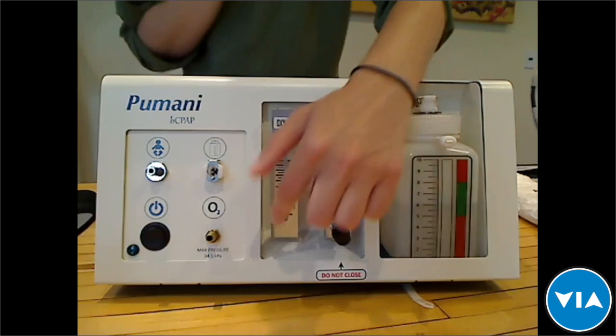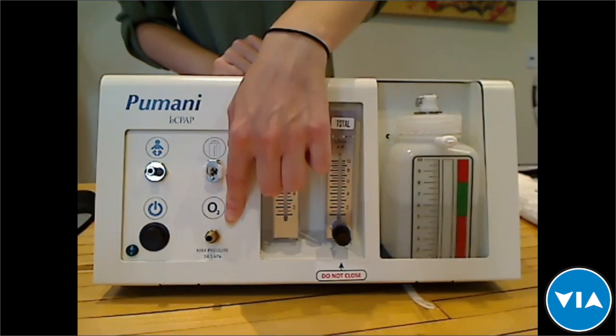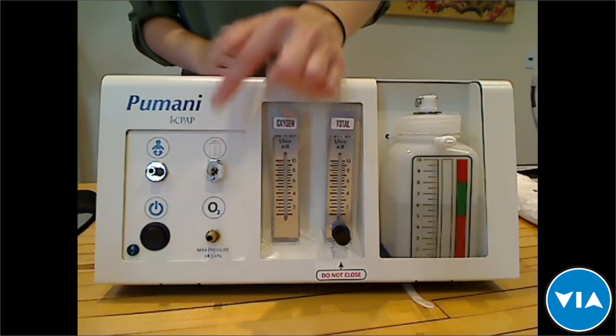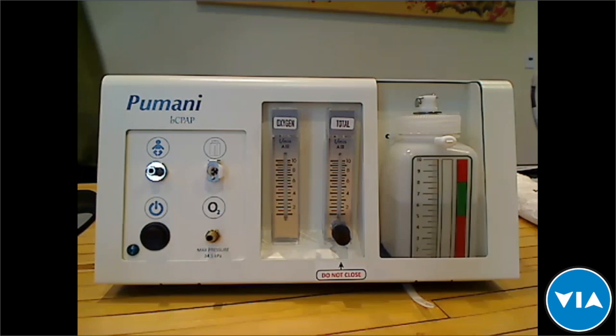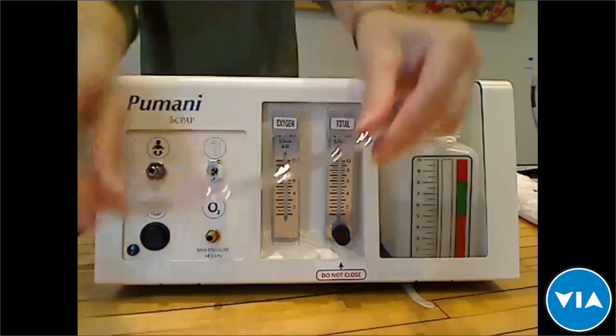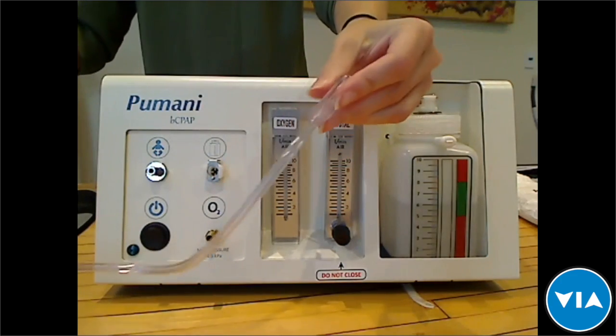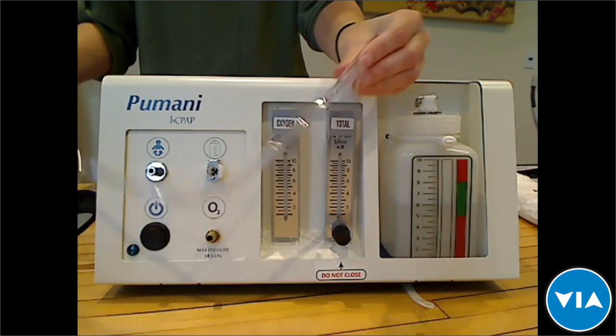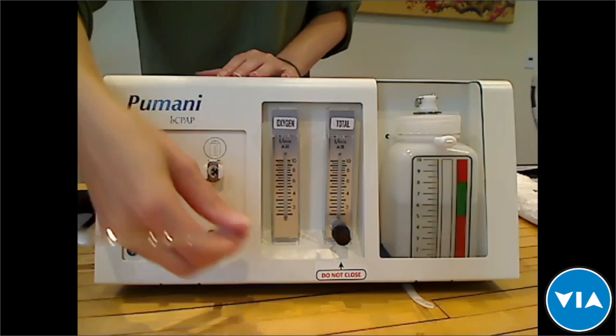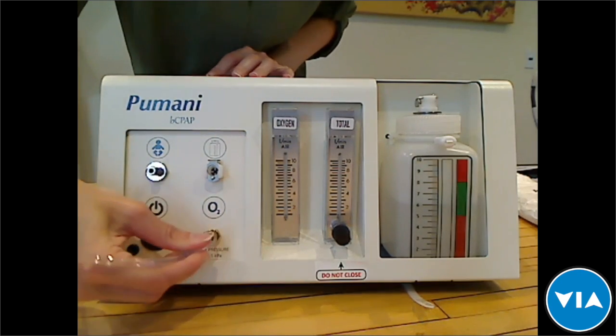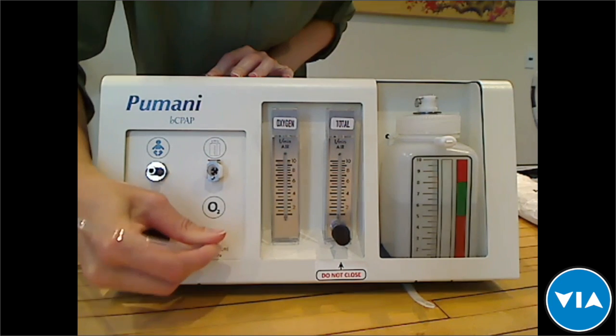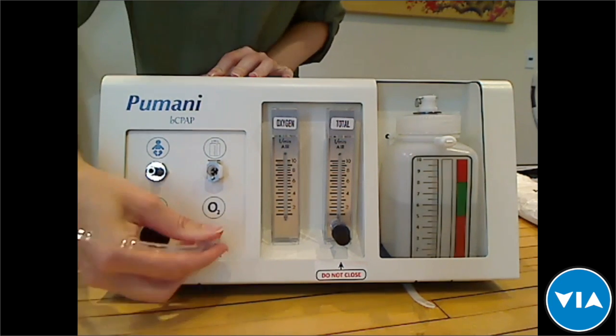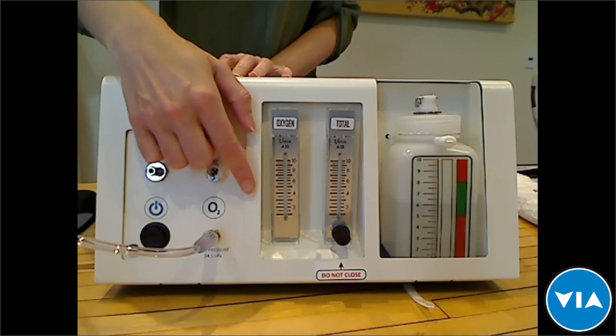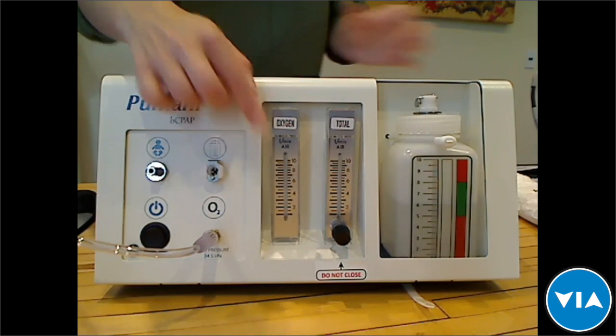So there is the oxygen port here where the oxygen tubing is attached. I'll just show you with oxygen tubing where that is attached. I have oxygen tubing here. This is on a concentrator, but it can be from a cylinder or from piped oxygen. And that would just connect to the port here. And you can read the oxygen flow on the oxygen meter here.